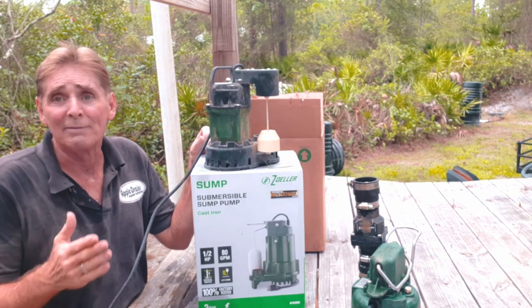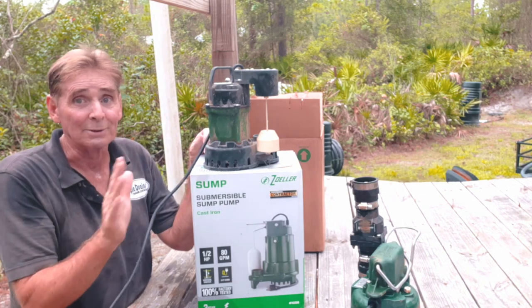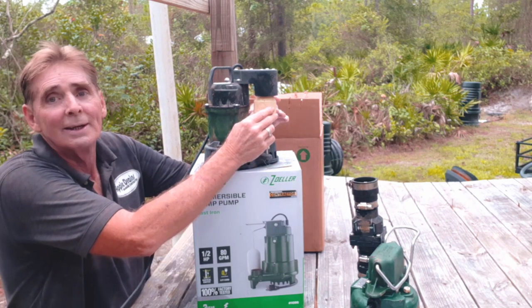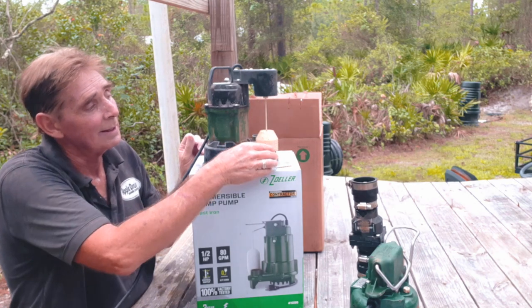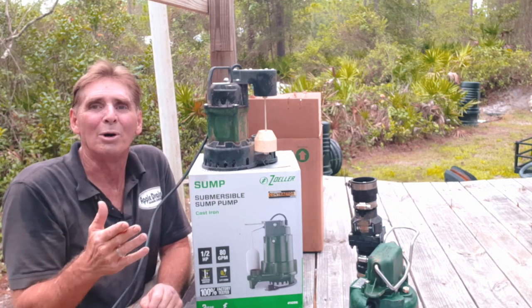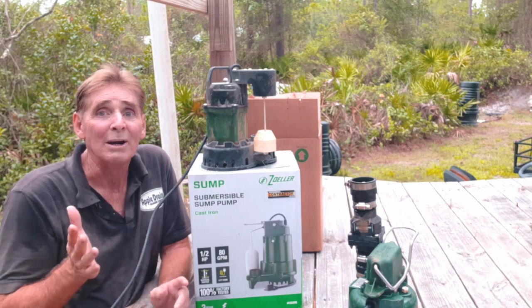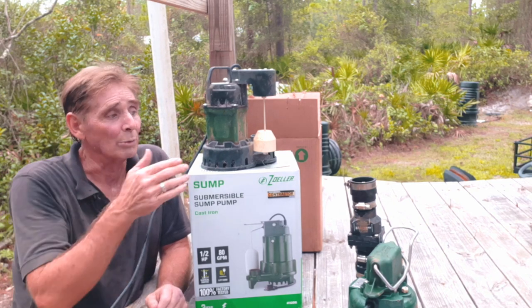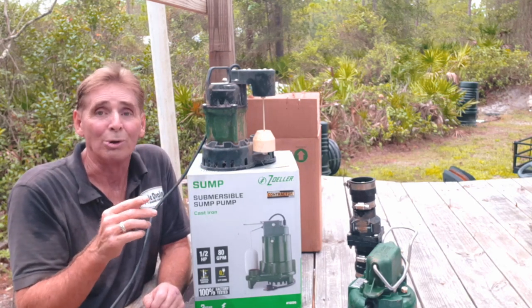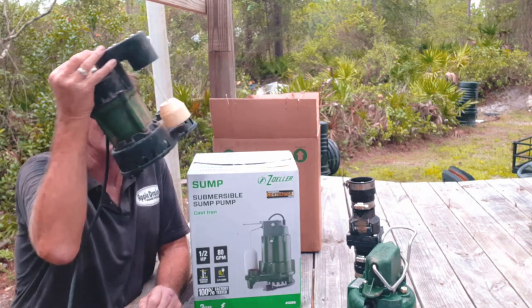Liberty's done the same thing, and I believe they have the same problem the H20 Pro had. It's off the market now — they don't sell it anymore. It has a magnetic float that comes up, and the pump kicks on, but it fails almost instantly. I put one in the first crawl space and within 10 days the customer called back saying they had a flood. The pump wasn't working, so we went straight back to using the Zoeller M98.